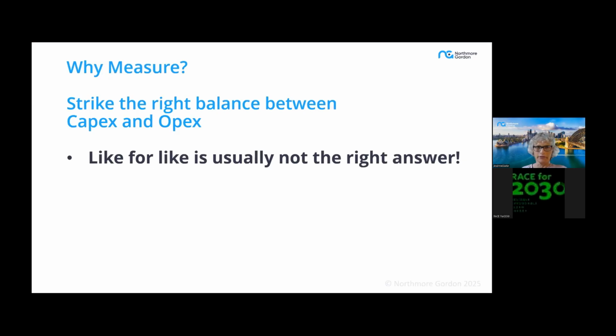So something that has been mentioned earlier on is that metering is important from a point of view of getting the right balance between CapEx and OpEx in a heat pump installation, and that like for like is not usually the right answer. That's because the cost of a heat pump is higher than that for a gas-fired boiler, and you want to make sure that you're matching your installation to the actual heat demand rather than oversizing it more than necessary.